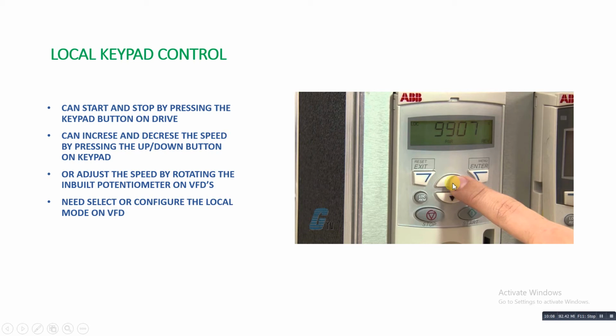Some VFDs also have an inbuilt potentiometer. By rotating that potentiometer you can increase and decrease the speed, or you can control the speed. As I told you, on some VFDs you have to configure the local remote selection, then only you can do the keypad on off system, or keypad start stop system.